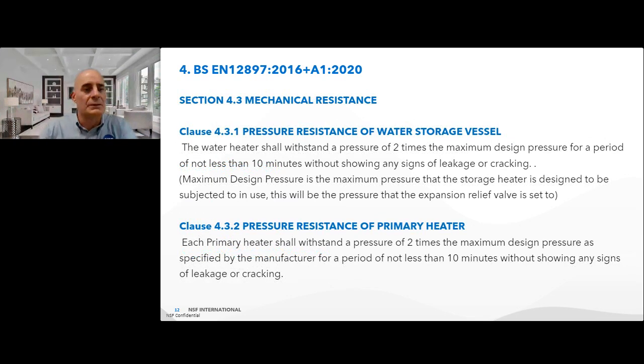Section 4.3, clause 4.3.1, so the pressure resistance of the water storage vessel. So this is the secondary circuit. The water heater should withstand a pressure of 2 times the maximum design pressure for a period of not less than 10 minutes without showing any signs of leakage or cracking. The maximum design pressure is the maximum pressure that the storage heater is designed to be subjected to in use. This will be the pressure that the expansion relief valve is set to. So for instance, if there's a 6 bar expansion relief valve fitted to the unit, then the test pressure will be 12 bar, twice the expansion relief valve setting.